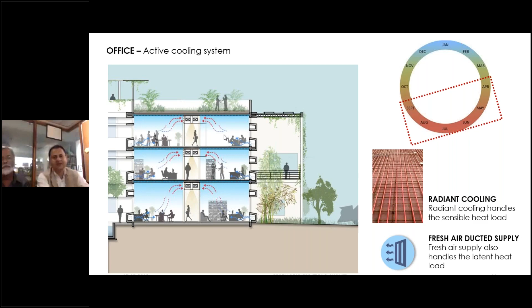Another impact of this whole design is that the system is provided with enhanced CO2 control levels. The beauty of this system is that none of the spaces ever exceed 800 ppm CO2, thanks to an additional 30% fresh air supplied from day one, with the AHUs designed accordingly. The AHUs also have PM 2.5 filters that ensure indoor air quality always remains above expectations.